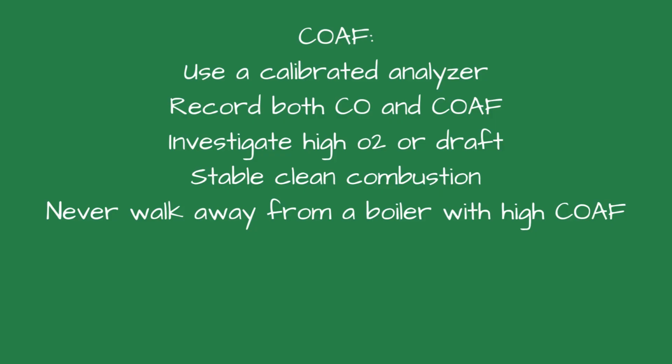Never walk away from an appliance with high CO air free, even if the measured CO looks harmless. The burner is actually making a dangerous amount of CO. The high excess air is just masking it.